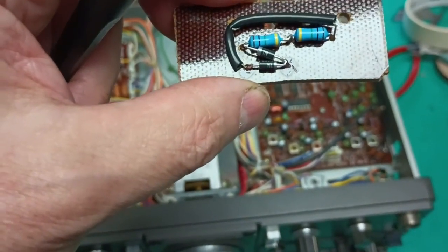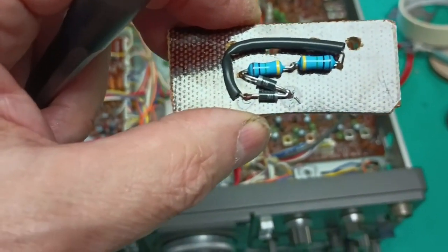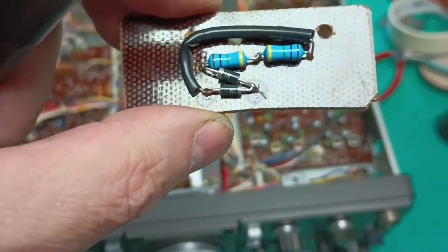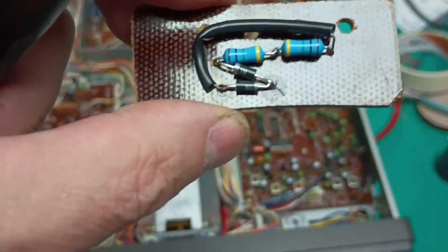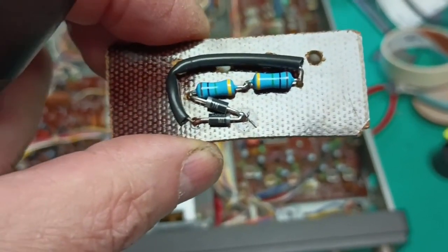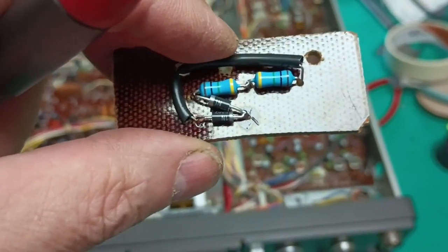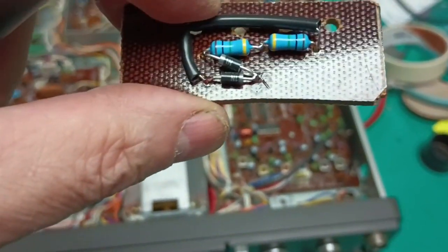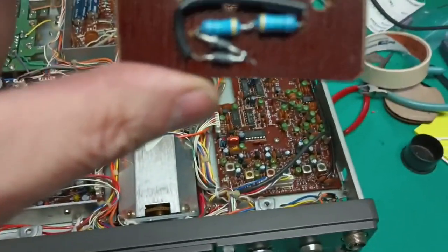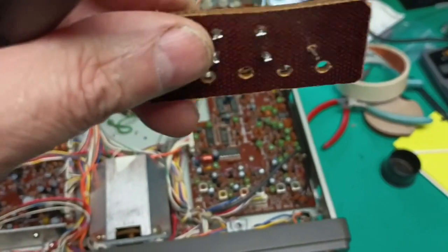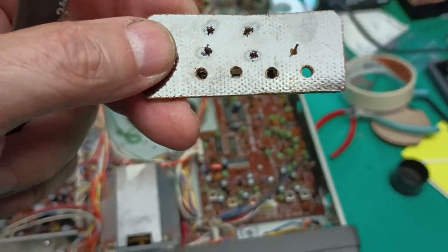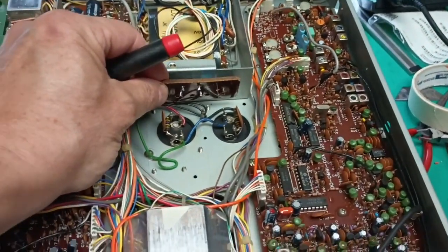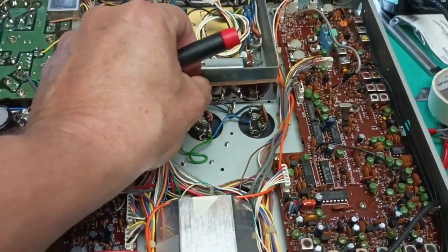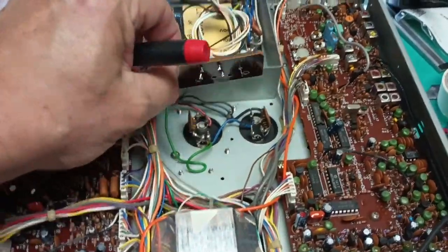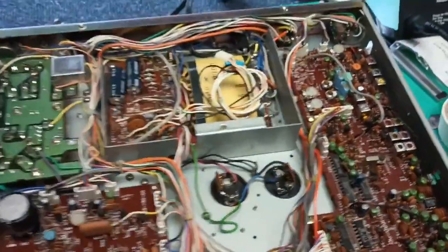So all that's going to be replaced with this. 2 1N4007s, 2 Mongo high voltage divider resistors, 1 meg each at 3 kV, so way overrated, and the 100K resistor at the low voltage end of ground is in this spaghetti. But uber high voltage insulating board, wires through holes soldered, and that'll go right in here against that somehow. And then the wires will solder to the exposed leads there, and then put some plastic insulation over it.